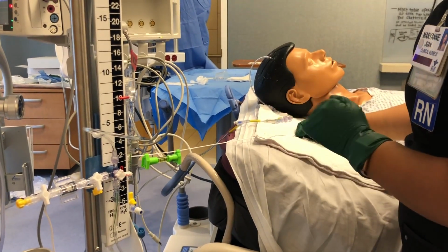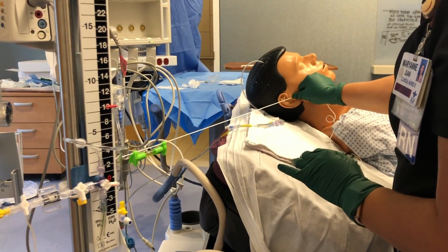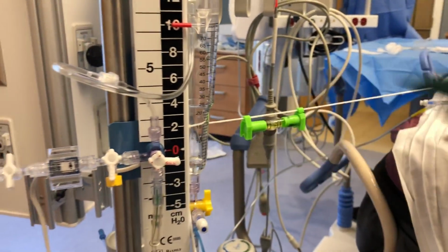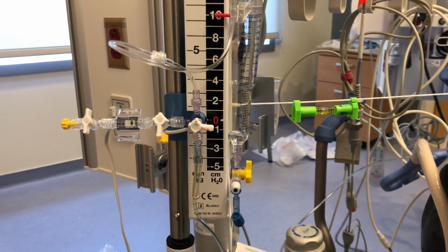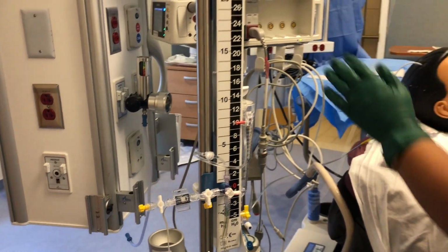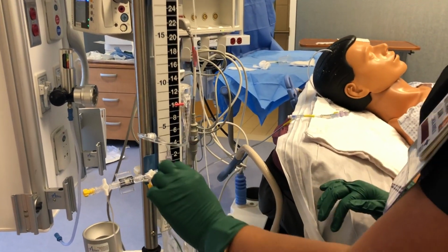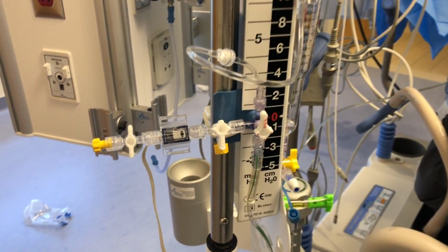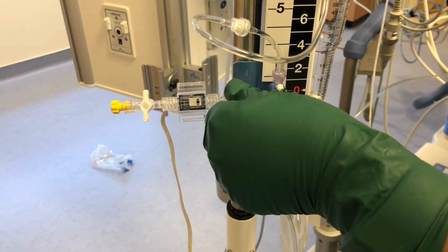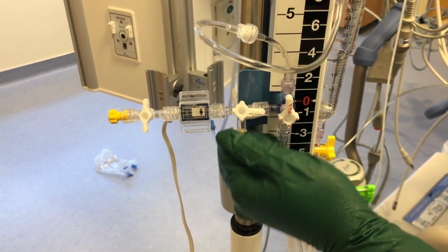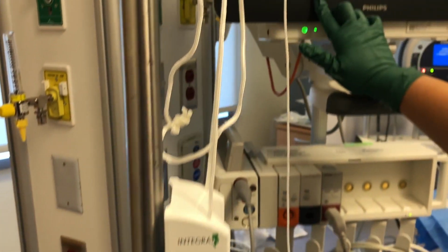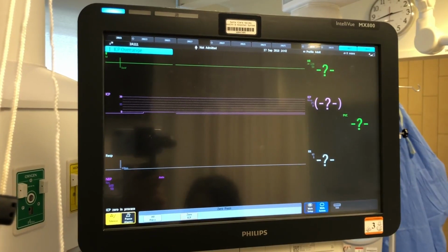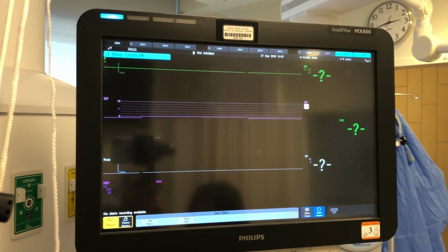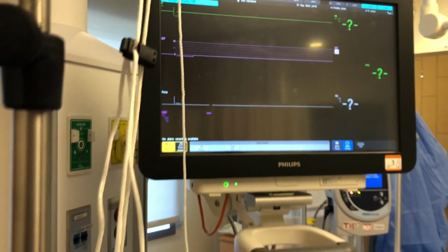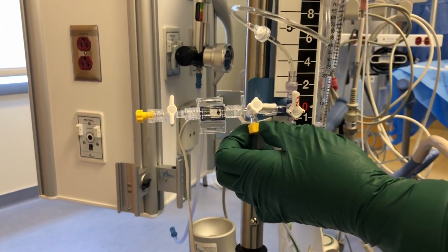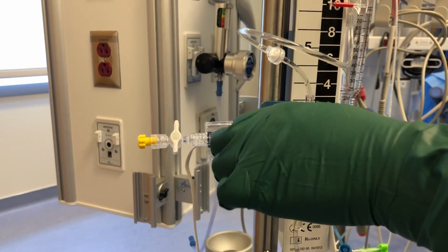So you have to zero the EVD every shift, and to do that, again, you have to make sure that the EAC is leveled with the 0. So right now, the bubble is in between the two lines. And then you turn off the stopcock to the drain, and then you turn off the transducer to the patient. You remove the screw, and then you press 0, 0 ICP, and then once the number reaches 0 and says ICP 0 done, you can go ahead and reconnect the screw, turn the stopcock to that.